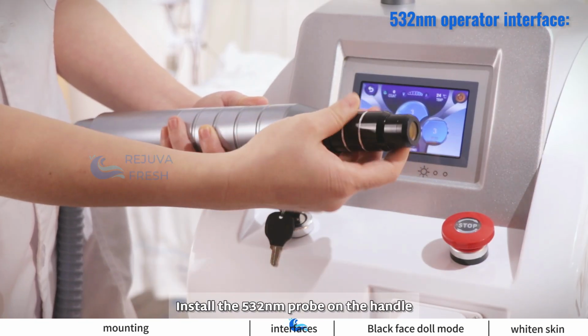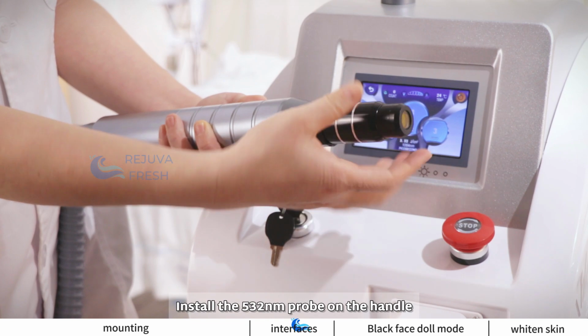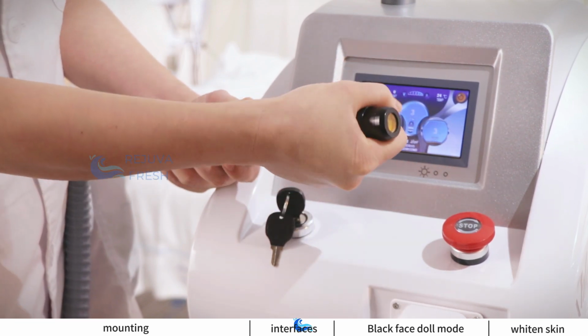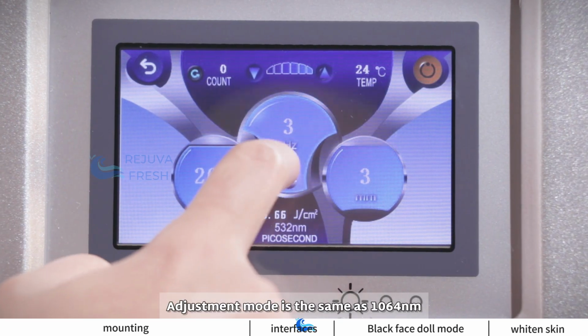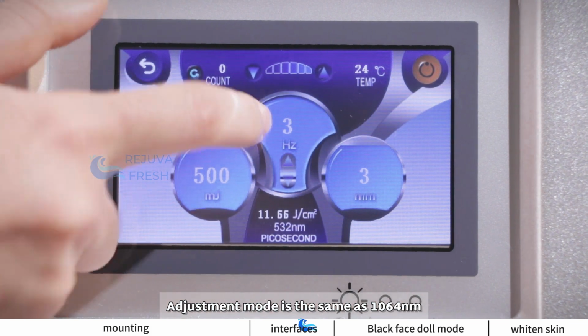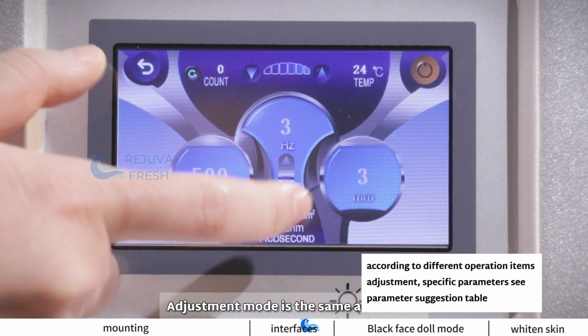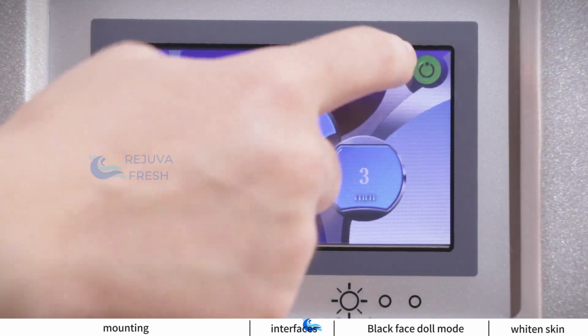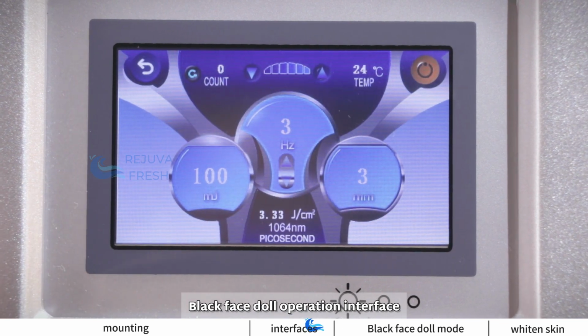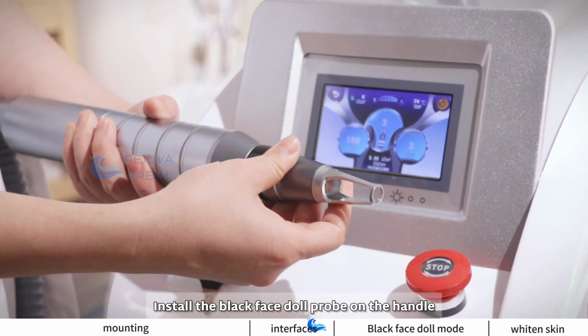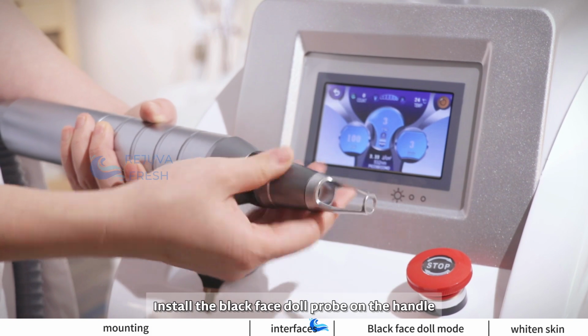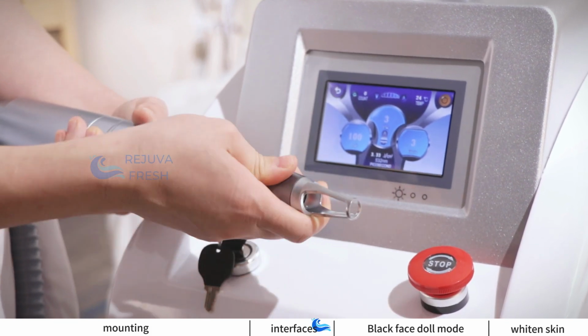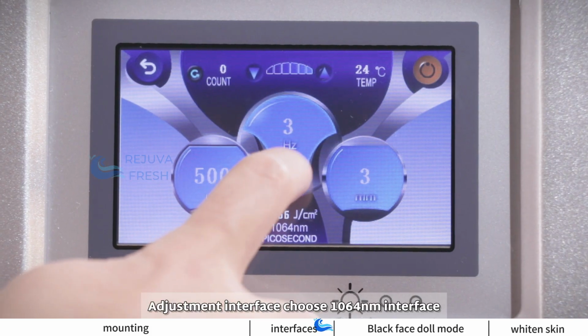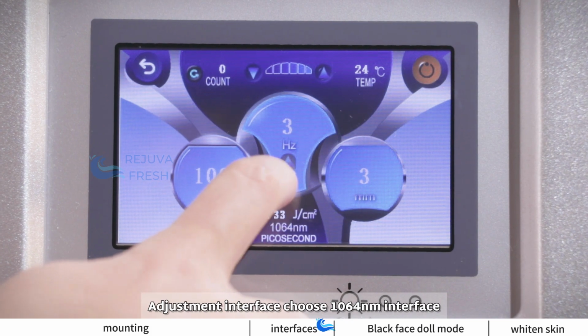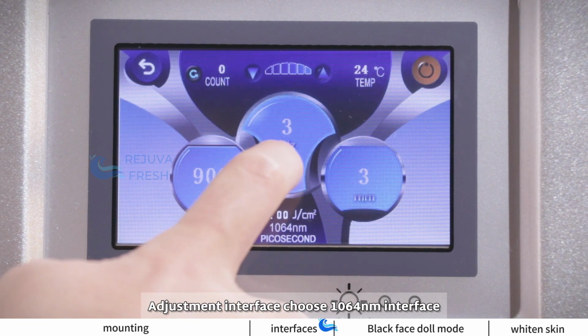Install the 532 nanometers probe on the handle. Adjustment mode is the same as 1064 nanometers. Black face doll operation interface. Install the black face doll probe on the handle. Adjustment interface. Choose 1064 nanometers interface.